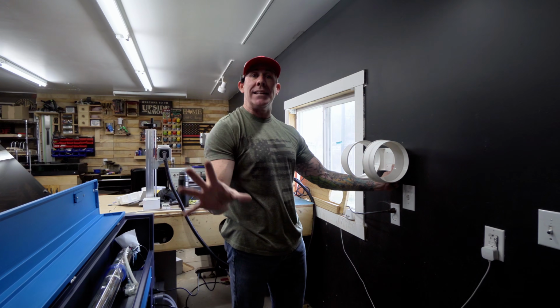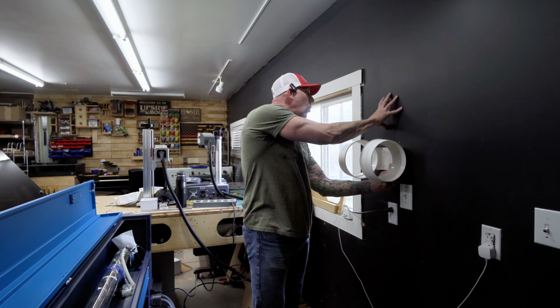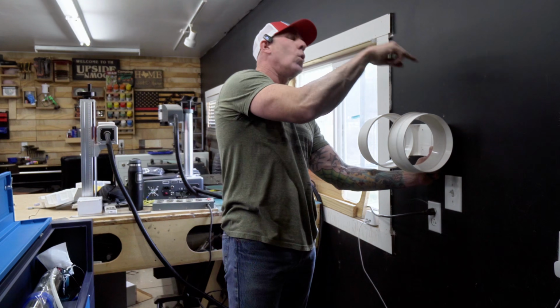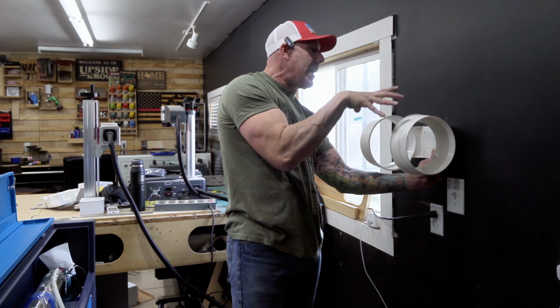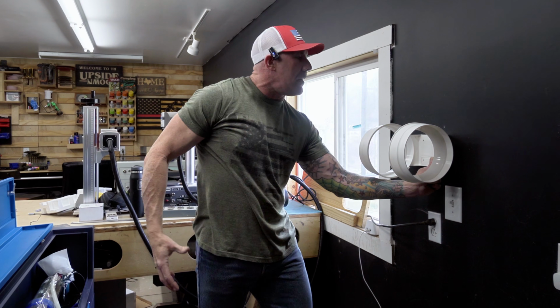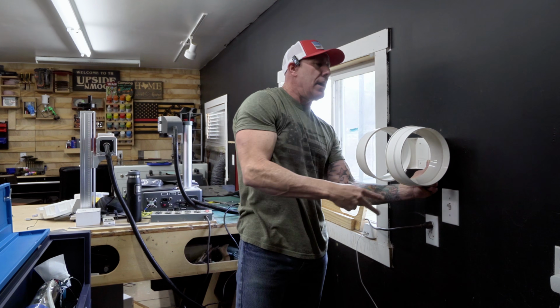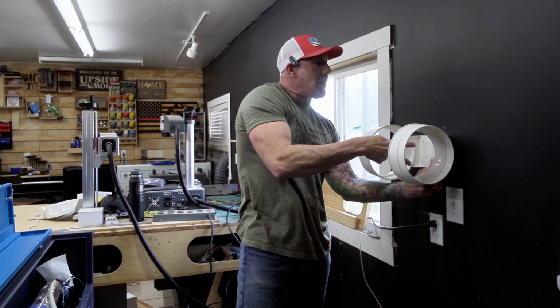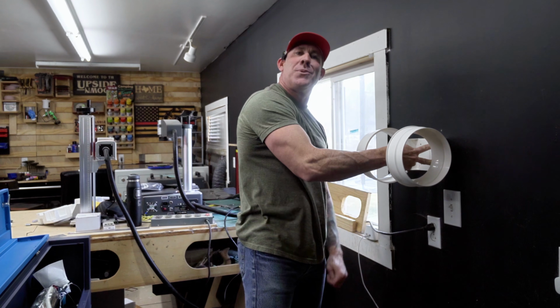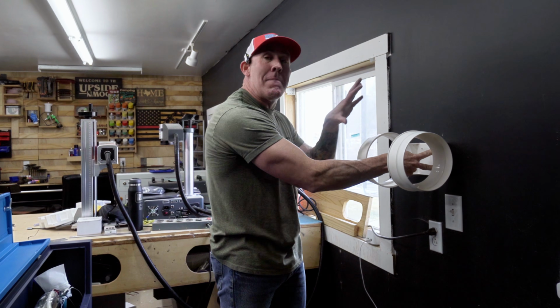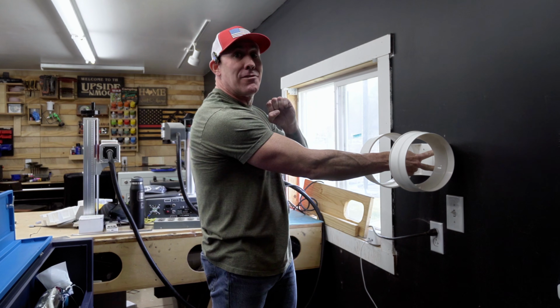Now let's go ahead and get this inline fan mounted to the wall close to our extraction point. You'll want to remove those two metal bands right here - that'll allow you to get the entire unit out and access the 4 holes. We've got a stud running right here, so I can get at least 2 of my screws into a stud. We're going to just temporarily mount this until we find a permanent location for it.